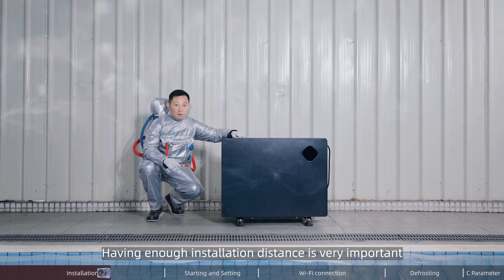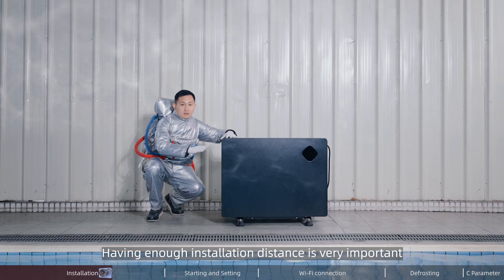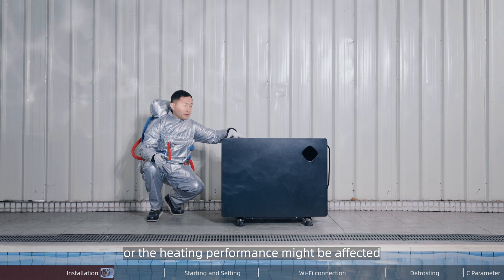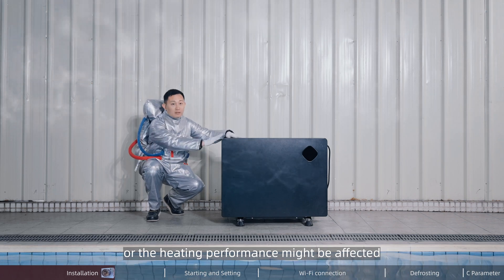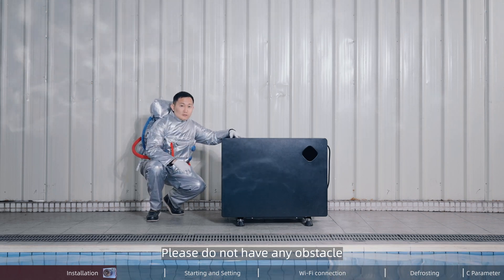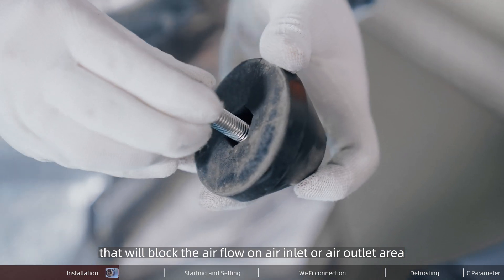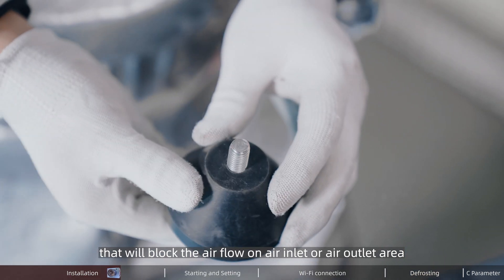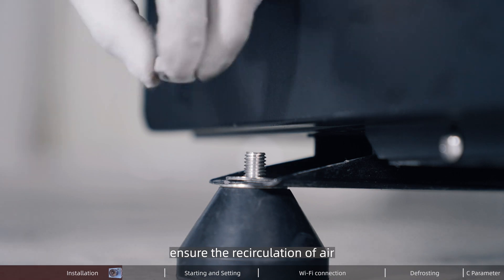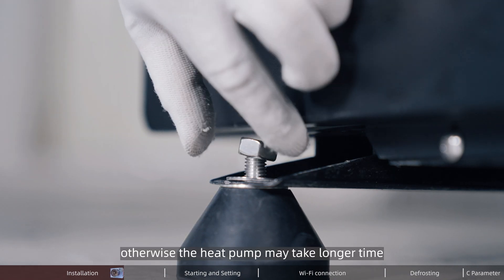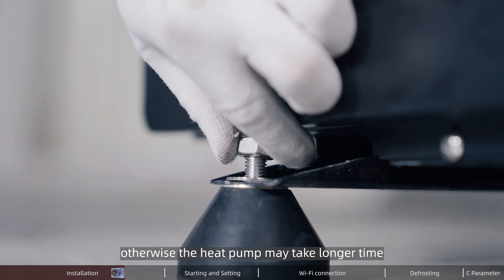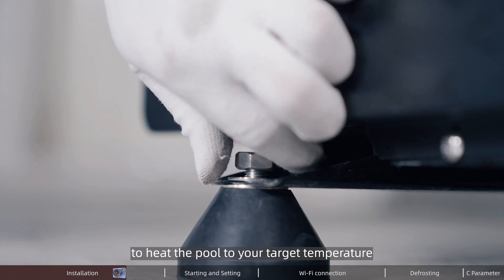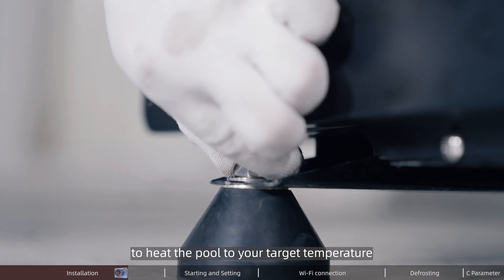Having enough installation distance is very important, or the heating performance might be affected. Please do not have any obstacle that will block the airflow on the air inlet or outlet area. Ensure no recirculation of air. Otherwise, the heat pump may take longer time to heat the pool to your target temperature.